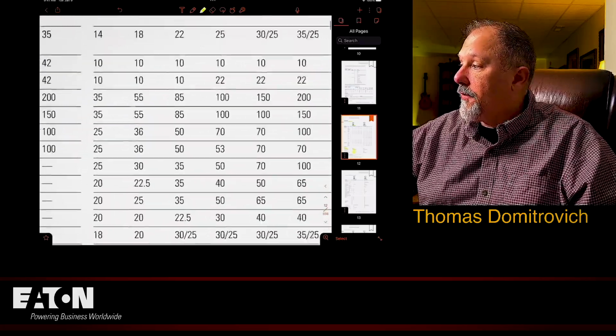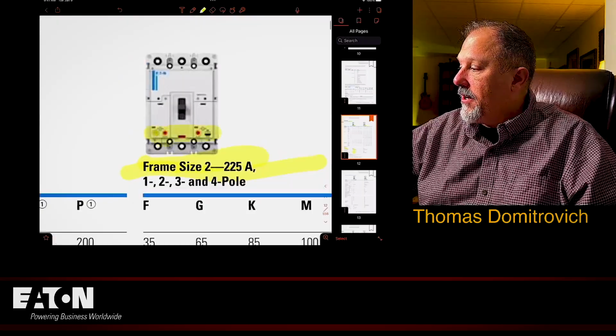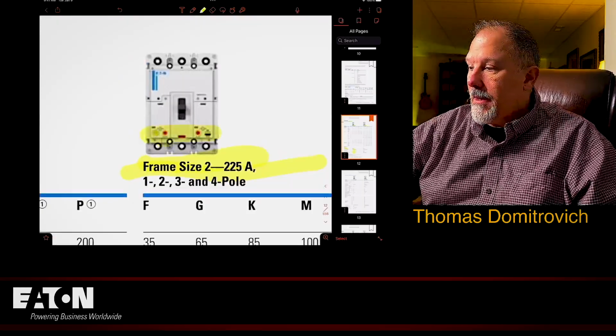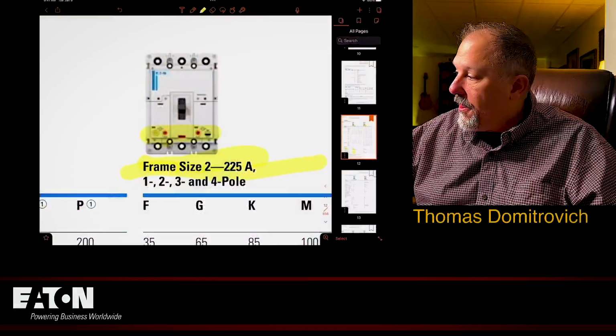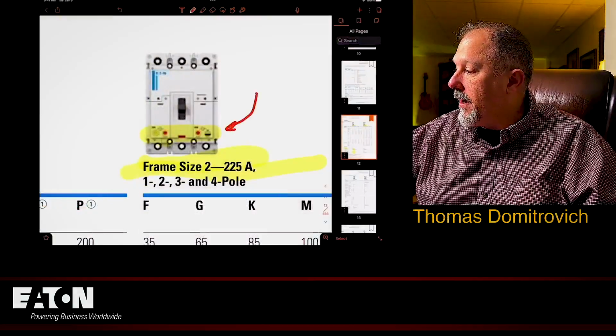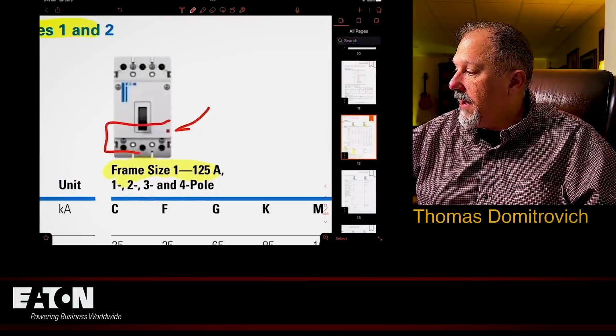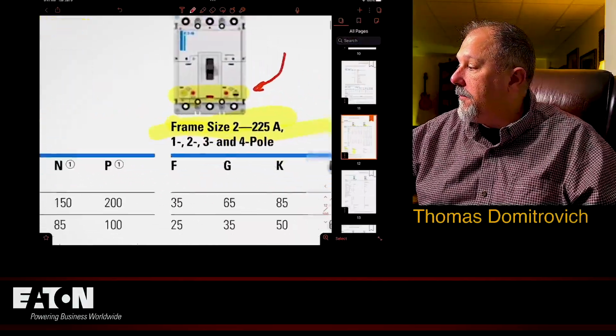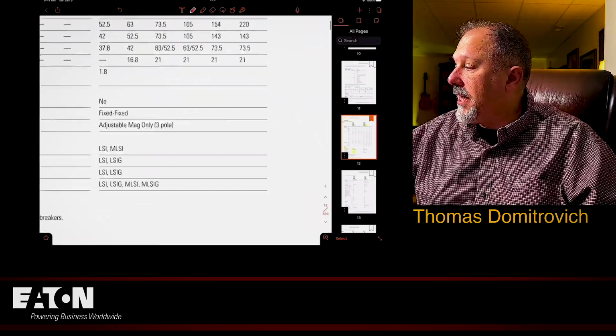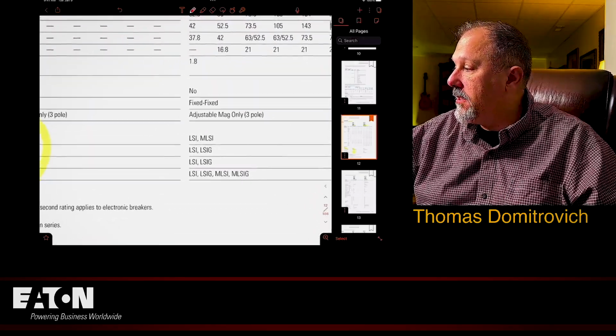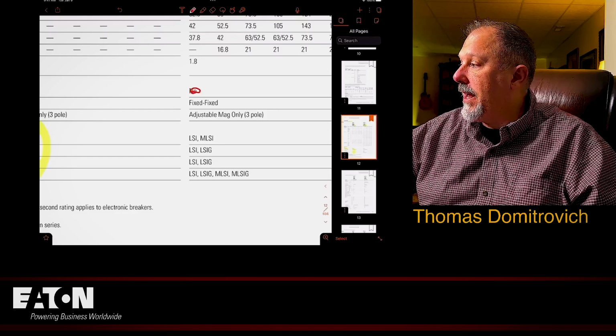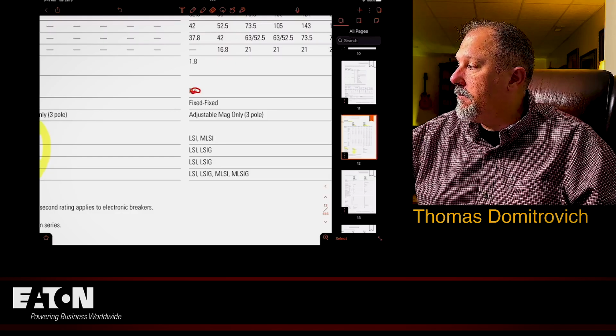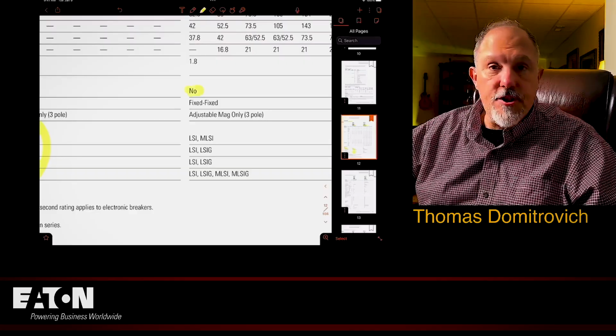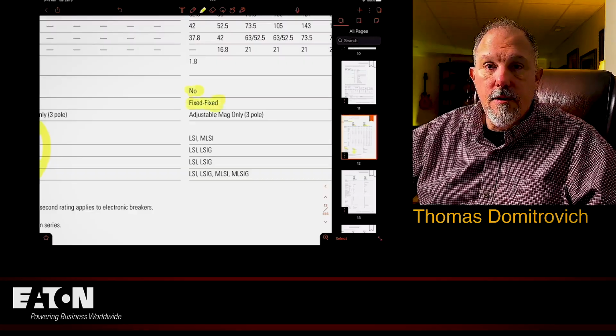Now you're getting a larger frame, and look, there's nothing down here for the electronic trip unit. Okay, this is the brain. This is what you're looking for. And this device does not have that capability right in there, right? This device does not have that capability right in there either. So, frame sizes. Now the functionality on this, okay, it doesn't have an interchangeable trip unit. Doesn't have an interchangeable trip unit. It's fixed thermomagnetic.